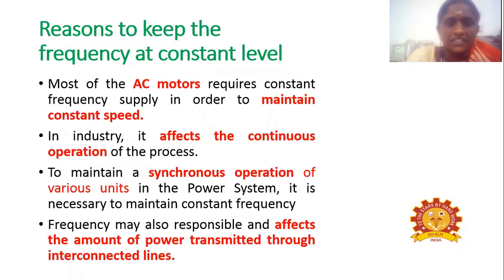Next we'll see the reasons to keep the voltage and frequency at a constant level. First, the reasons to keep the frequency constant. You all know that the motors we use are AC motors, which require constant speed operation. If the frequency deviates, it affects the continuous speed operation. In industry, it affects the continuous operation of the process. It also makes it impossible to maintain synchronous operation in power system networks. And a change in frequency affects the amount of power transmitted through the interconnected lines. These are some of the reasons why we need to maintain the frequency at a constant level.